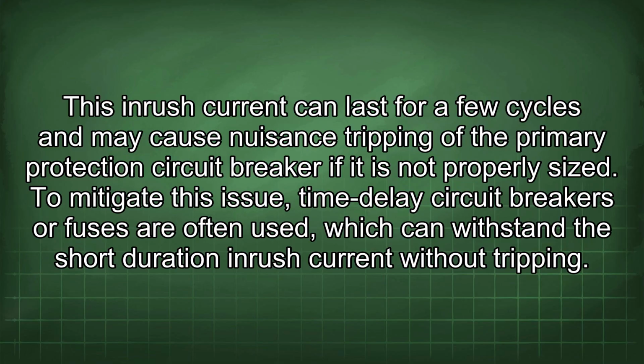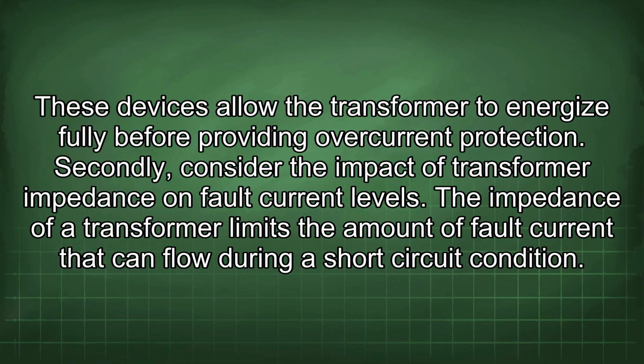To mitigate this issue, time delay circuit breakers or fuses are often used, which can withstand the short duration inrush current without tripping. These devices allow the transformer to energize fully before providing overcurrent protection. Secondly, consider the impact of transformer impedance on fault current levels.